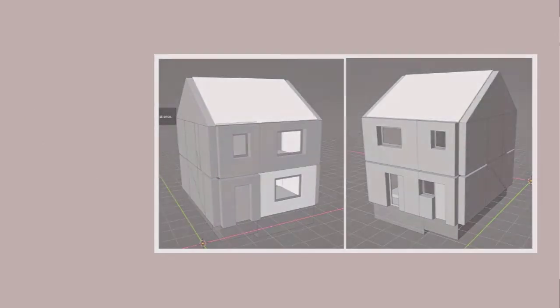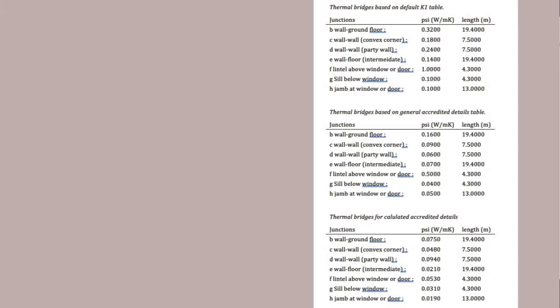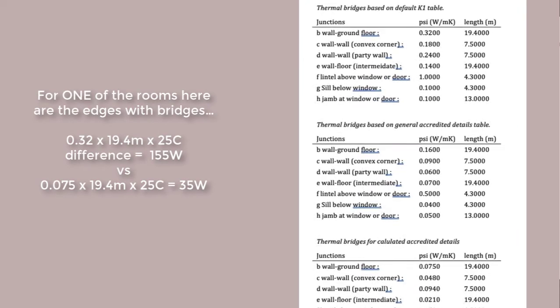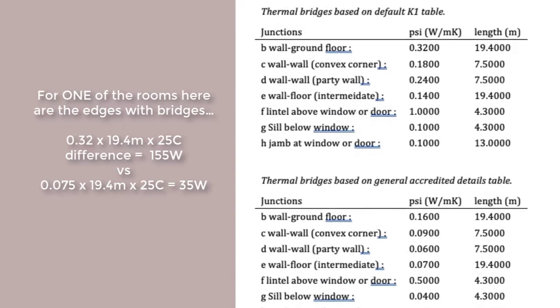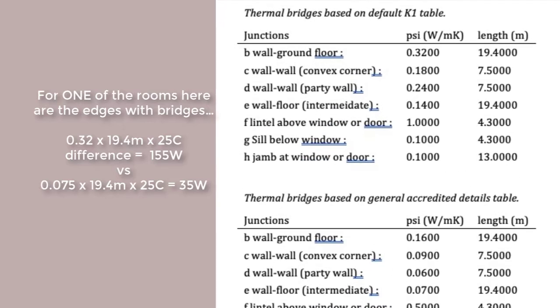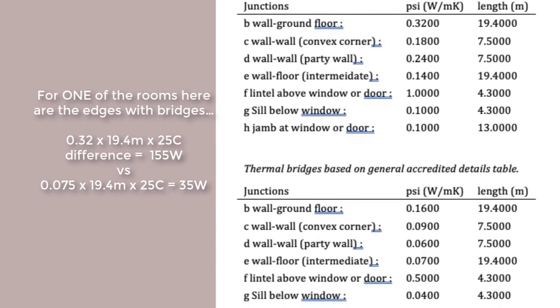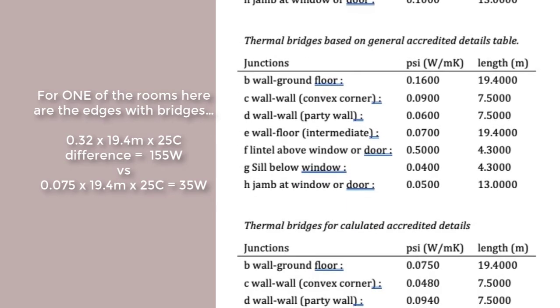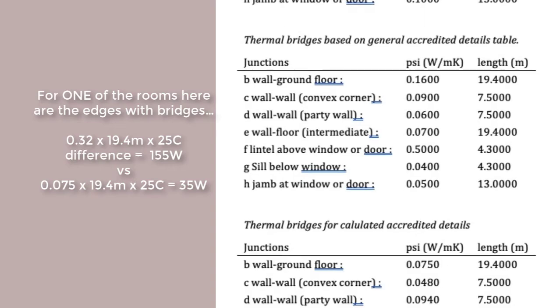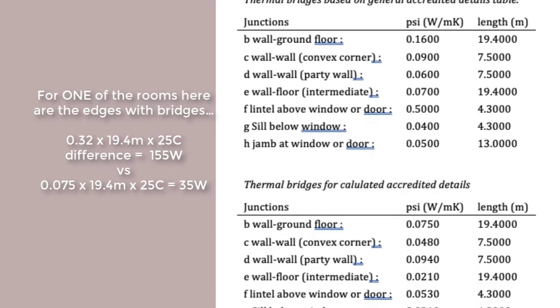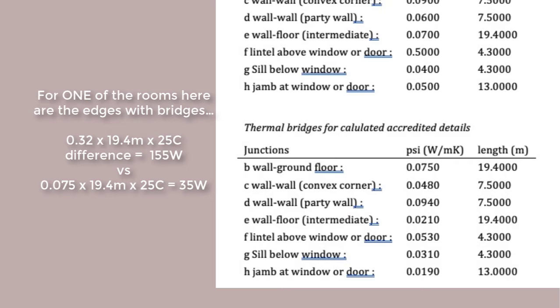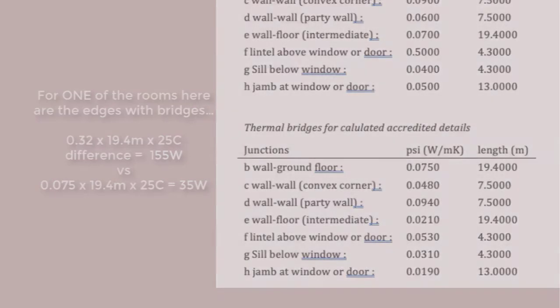A simplified treatment of thermal bridges takes the psi value times the length of the junction and the temperature difference with the outside. Using the default for a 19 meter length of wall to ground floor gives a heat loss of 155 watts. But if we can be bothered to design better, we can drop that to 35 watts. Passive House designs aim for a psi value of less than 0.01, which would equate to roughly 5 watts.